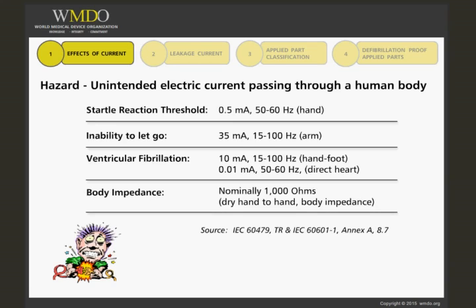The standard considers the body impedance, or the resistance that the body is considered to have, to be nominally 1,000 ohms. This is based on dry, hand-to-hand body impedance.